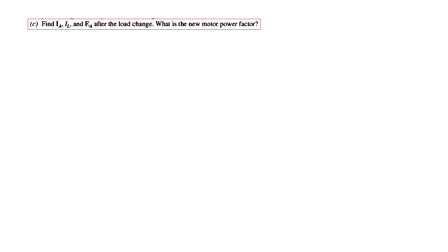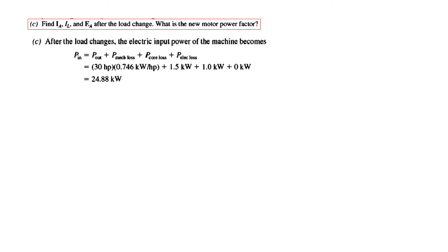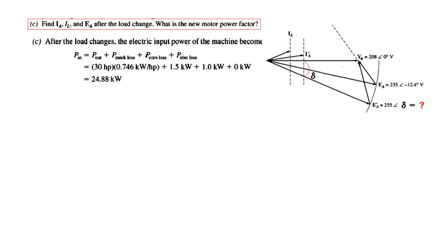Part 3 asks us to find the new Ia, Il, and Ea after the load increases to 30 hp, and to calculate the new power factor. We convert 30 hp to electrical power: 30 × 0.746 = 22.38 kW output. Adding the same mechanical and core losses, the new input power is 24.8 kW.